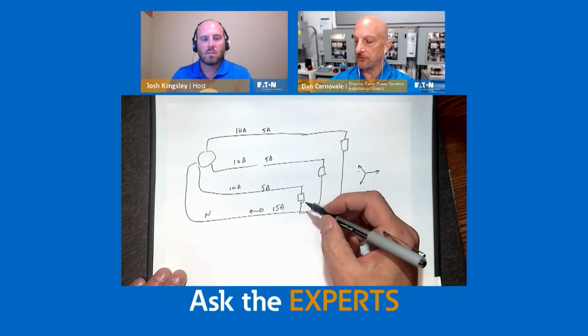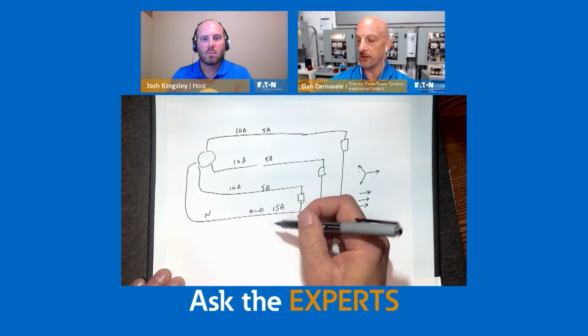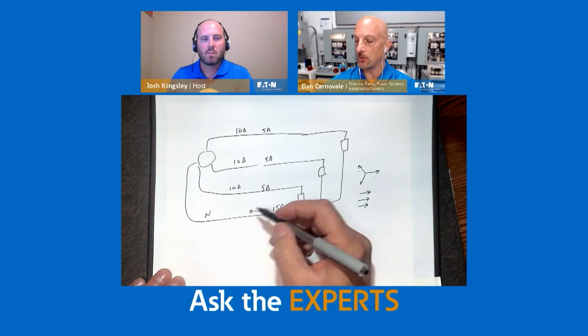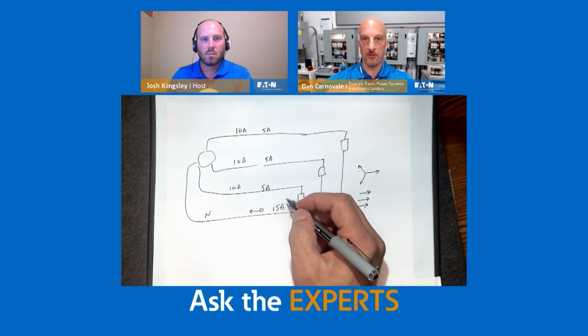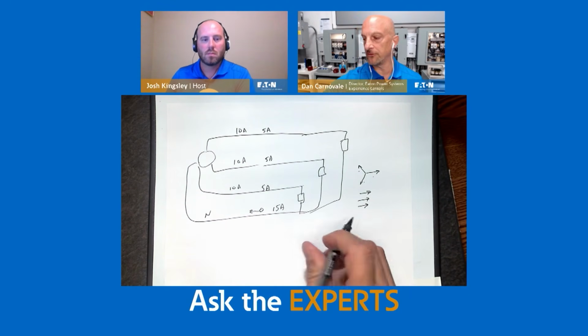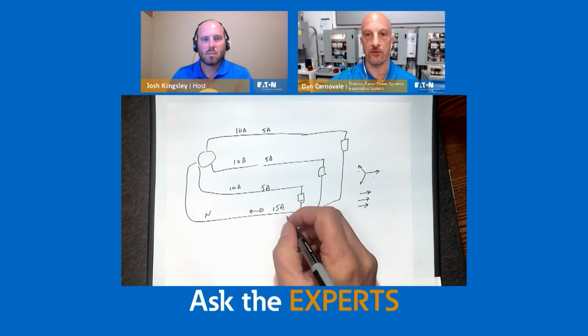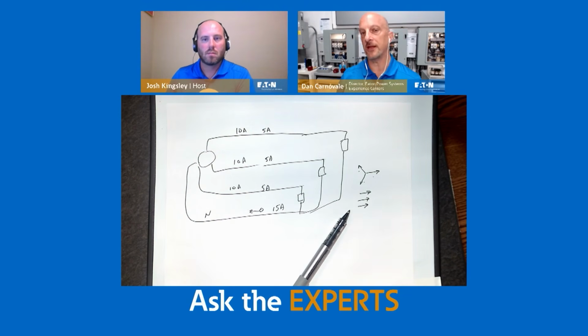what you're referencing is you're talking about a medium voltage system and a 480 volt system that doesn't have a neutral. So in this case, we're not talking about those type of low frequency, in this case, third harmonic, for example, zero sequence harmonics. What you're talking about, I think, is some of the higher frequency harmonics. And those can come from sometimes the outputs of VFDs, the pulse width modulated output.